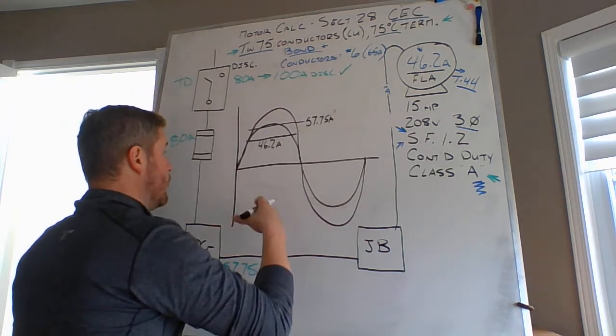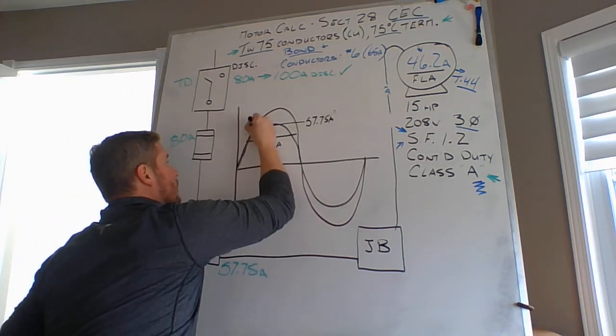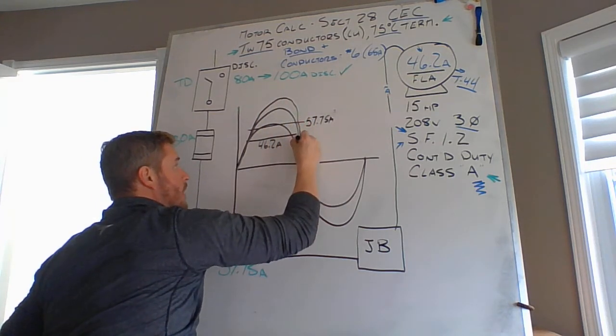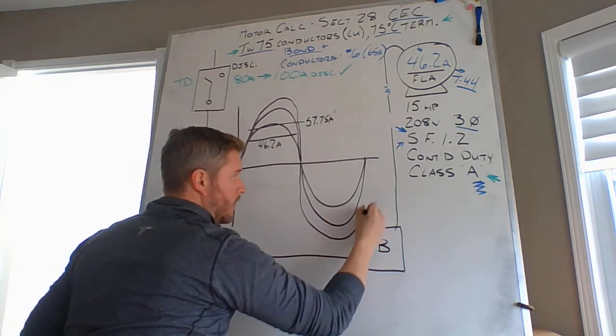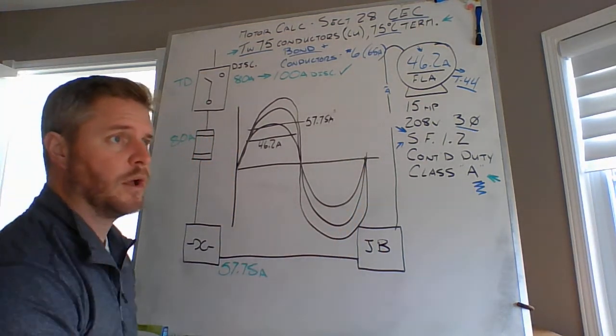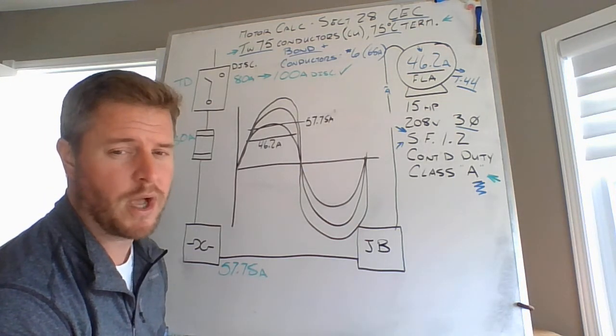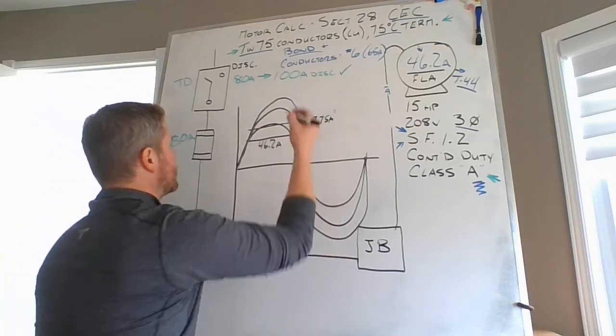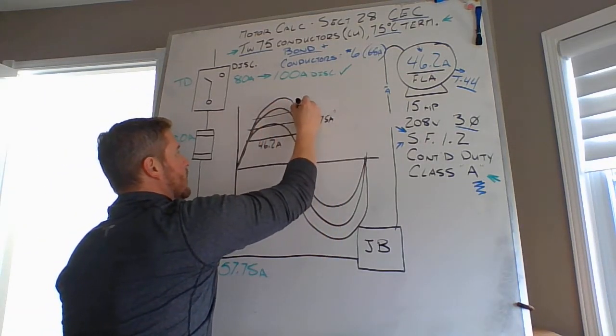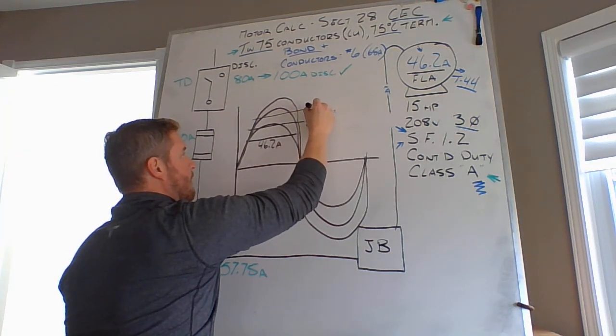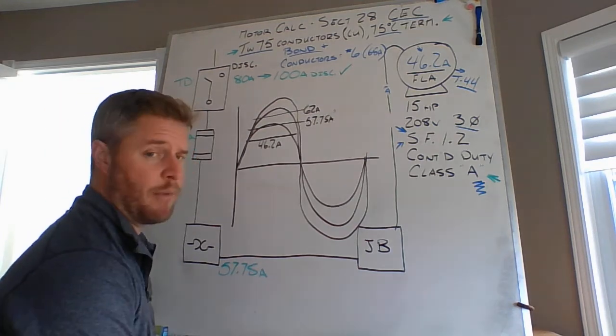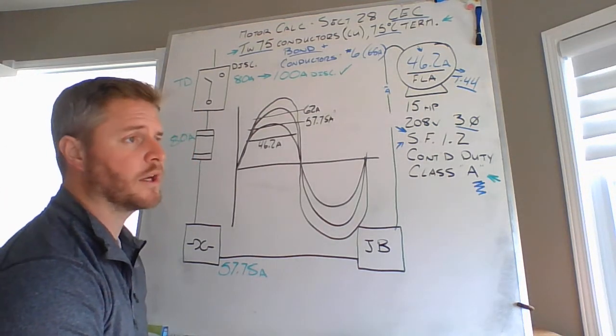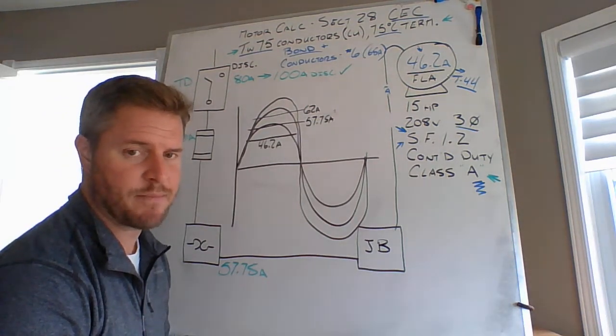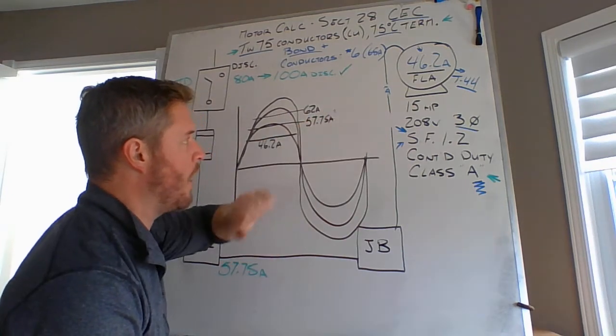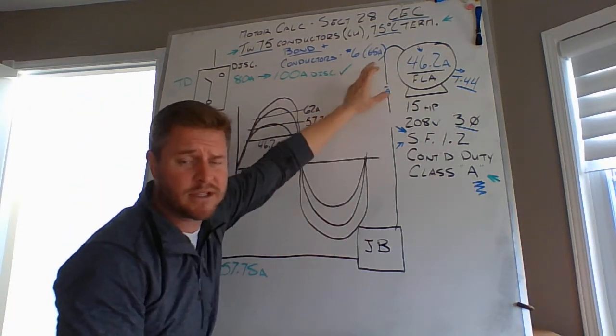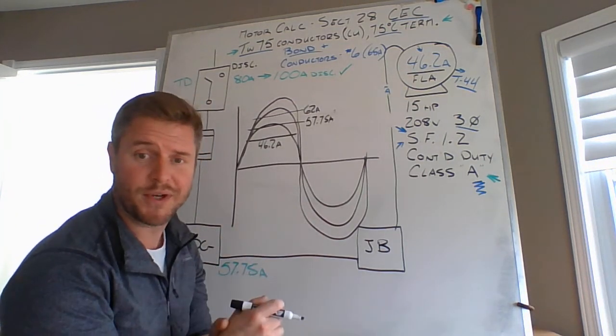And then as soon as you force that motor to draw even more, anything slightly above and beyond 57.75 amps, your overloads are going to say, okay, listen, that's too much. We're not going to do that anymore. So you might get up to, I don't know, maybe the 62 amp mark up here. That's too much on that motor. Your overloads are going to say, no way, man. You're drawing too much on this motor. I can't let that motor do that work any longer. My conductors are getting really close to their capabilities. No, I'm out. And they open the control circuit.